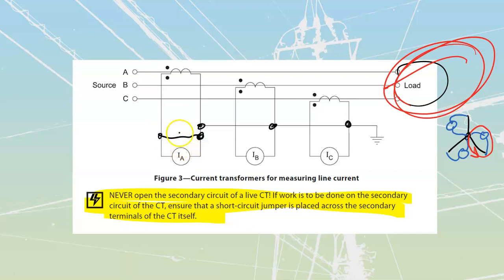This is not a load transformer, this is a measurement transformer. In other words, the load controls the amount of current going through the main lines, which in turn controls the amount of current generated through here. You can place a shorting bar across here because you're guaranteed that at no point is there ever going to be more than 5 amps flowing through this little loop.